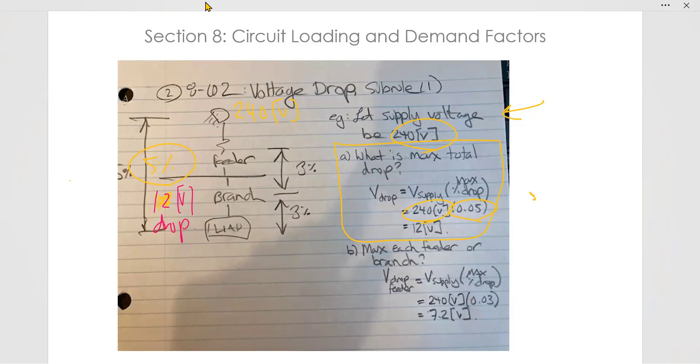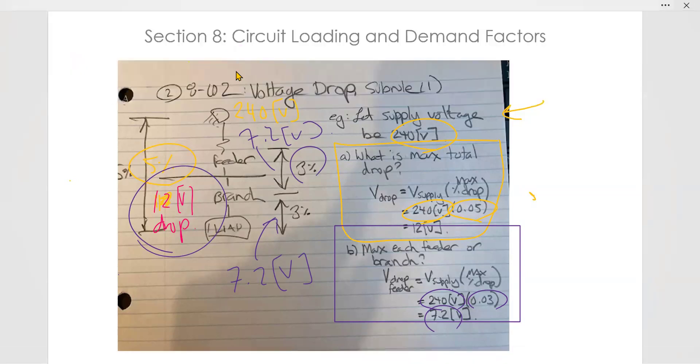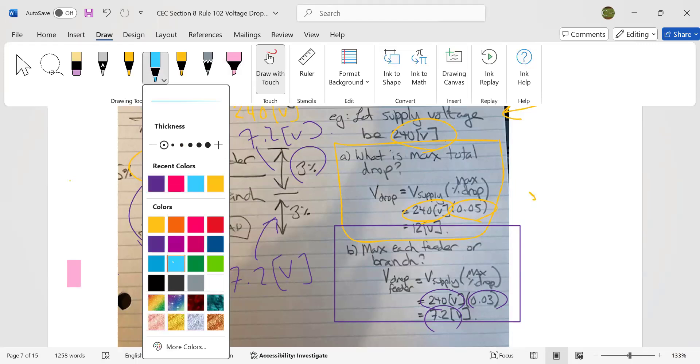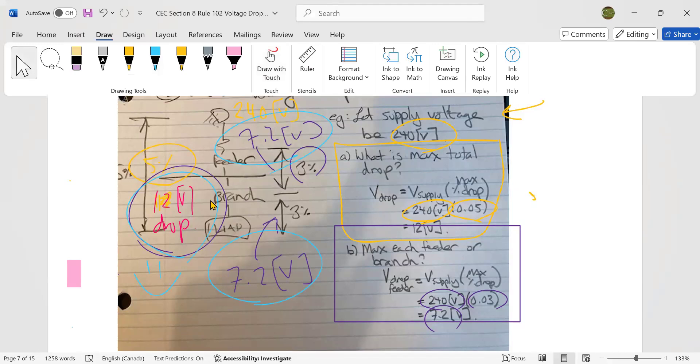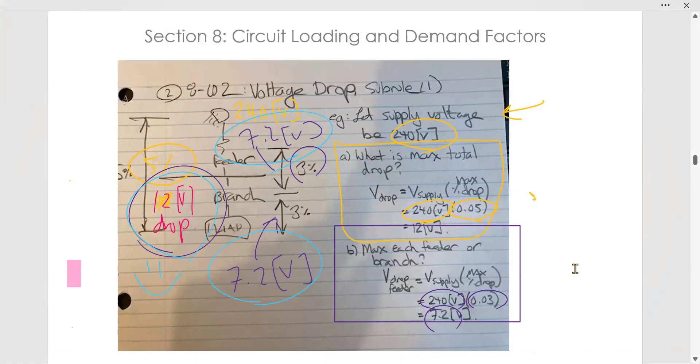I just calculated 5% of 240. And then what is the maximum each in each feeder or branch circuit? Well, then it is the supply voltage. Again, it's 240 times 3%, 240 times 3%. So that's 7.2. So this cannot drop more than 7.2 volts. And this cannot drop more than 7.2 volts. And you cannot drop more than 12 combined. So if this is going to drop 7.2, if we're going to drop 7.2 in the branch, then we cannot drop 7.2 in the feeder because it would be more than 12. So this has to be observed, the 12 voltage drop here. And that's how subsection 1 of rule 8.102 works. So a nice little example problem. Make sure that you understand that.